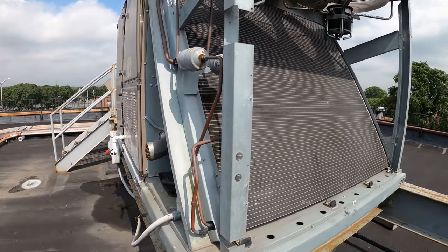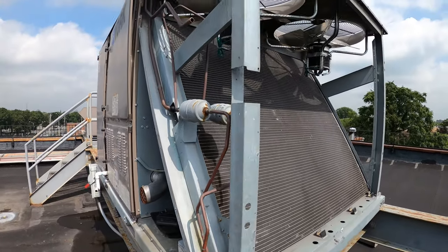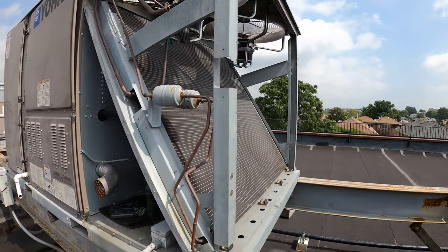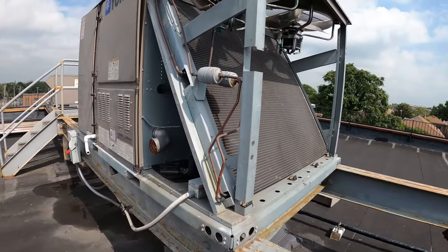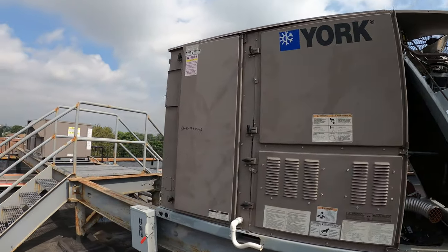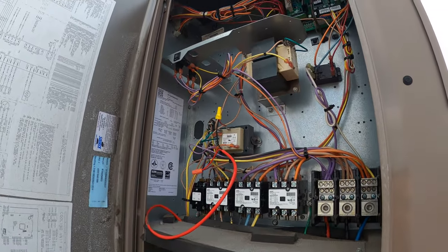That's a beautiful thing. All right everyone, that's pretty much how you remove the coil. Typically you would have to hook up your gauges and recover the refrigerant, but with a broken pipe like this all the refrigerant already leaked out. We disconnected the screws, supported the fan, and roped the coil off the roof. I'm going to make the installation a separate video as there are quite a few processes to cover. If anybody found this video interesting or helpful, please drop a like, comment, and subscribe — I'll catch you all next time.